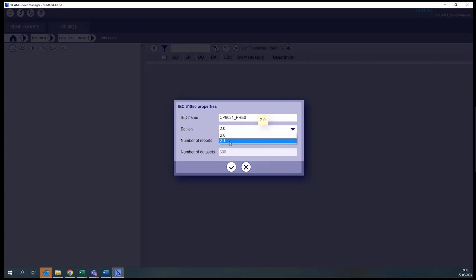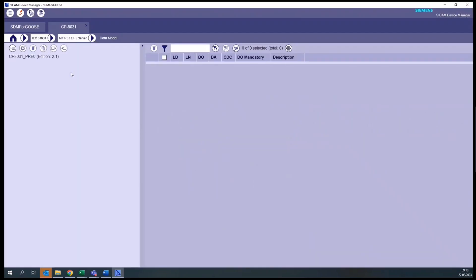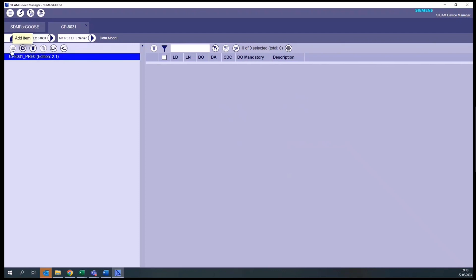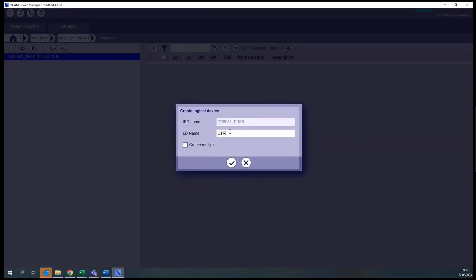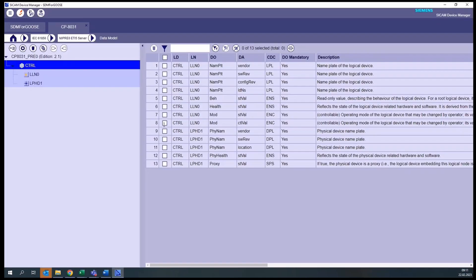The firmware supports version 2.0 or version 2.1 — we can select either one. We confirm and save the status. Now we create at least one logical device for this IED. For this example, let's name it 'Control'. Now that we have this logical device, we can create logical nodes to receive the information. Click on the created logical device Control, and then on the Add Item button.